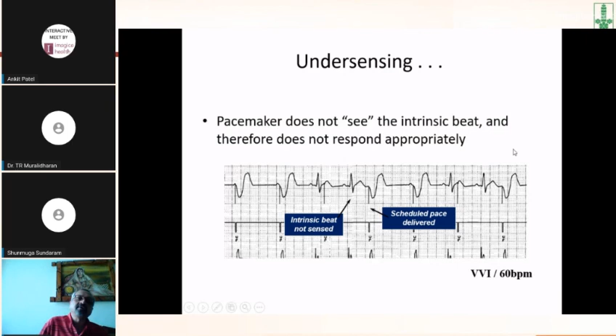And in the fourth beat, again, after the T wave, a pacing spike has come. The marker channel all the time shows a ventricular paced beat. So VVI at 60 beats per minute, the pacemaker does not see the intrinsic beat, just keeps firing inappropriately. The danger in such a pacing system is a pacing spike falling on the critical refractory phase of the cycle, causing what's called an R on T PVC and triggering VT, which is not desirable. Next.